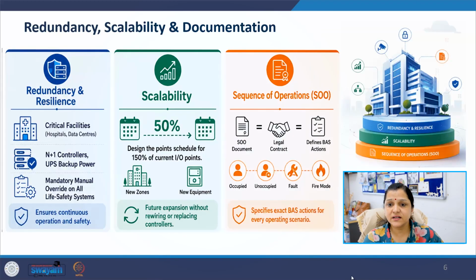Next is redundancy, scalability, and documentation. A professionally designed building automation system must also consider redundancy and future expansion. Critical buildings such as hospitals and data centers cannot depend on a single controller. Therefore, backup controllers, UPS power supply, and manual override systems are essential. Another important concept is scalability. Designers often underestimate future growth. A good practice is to design for approximately 150% of current input output points. This allows future expansion without replacing the entire infrastructure.